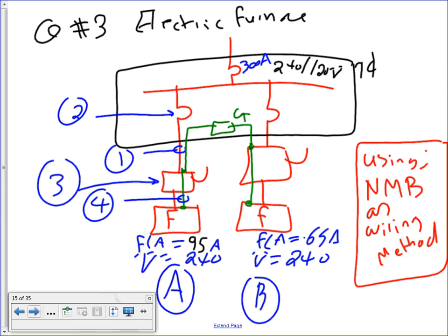I need to size the overcurrent protection device, the conductor, the disconnect for that heater, and the equipment grounding conductor. I'm still using the worst cable that I can do, which is NMB, and the wiring method is Romex. Voltage is 240/120, and the panel says it's 300 amp. We're going to do the same calculation as for our water heater. Do you guys see what we're trying to achieve? I know you're beginners to the design yet. That's what you're going to be asked. They give you different loads and you size them.